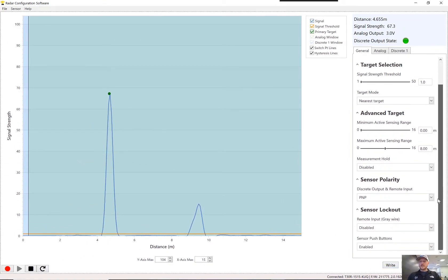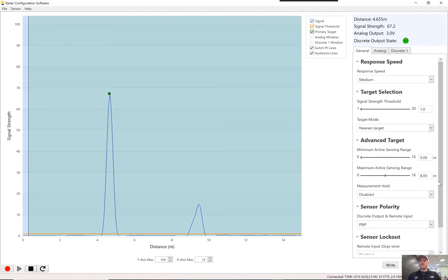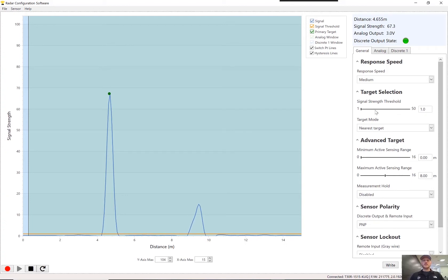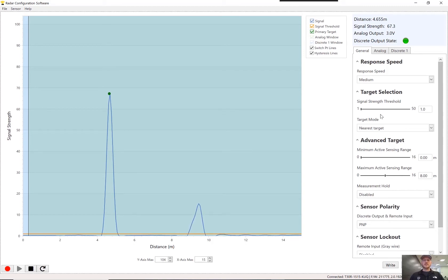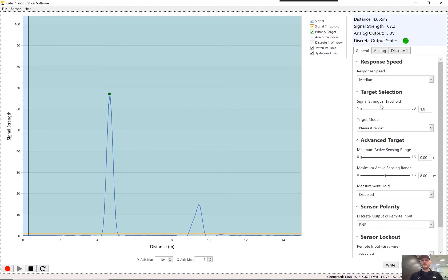And this is where you can kind of set up your sensor polarity, enable the push buttons, that type of thing. This is your signal strength. And typically one is the default, and that's typically where you would have this set. I would say that if you're in very heavy rain or foggy conditions, you might have to bump up that signal threshold value to a little bit higher level to ignore really heavy falling rain and that kind of thing.